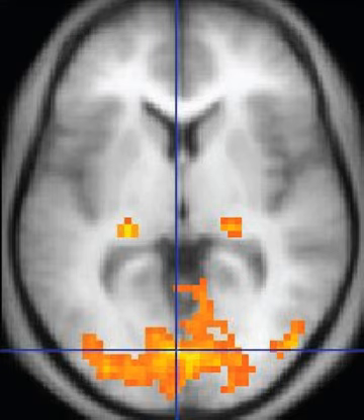Magnetic resonance spectroscopy is used to measure the levels of different metabolites in body tissues. The MR signal produces a spectrum of resonances that corresponds to different molecular arrangements of the isotope being imaged. This signature is used to diagnose certain metabolic disorders, especially those affecting the brain, and to provide information on tumor metabolism. Magnetic resonance spectroscopic imaging combines both spectroscopic and imaging methods to produce spatially localized spectra from within the sample or patient. The spatial resolution is much lower, but the spectra in each voxel contains information about many metabolites. MRSI requires high SNR achievable only at higher field strengths, and high procurement and maintenance costs of MRI with extremely high field strengths inhibit their popularity.